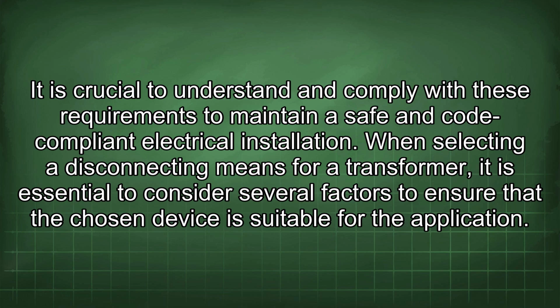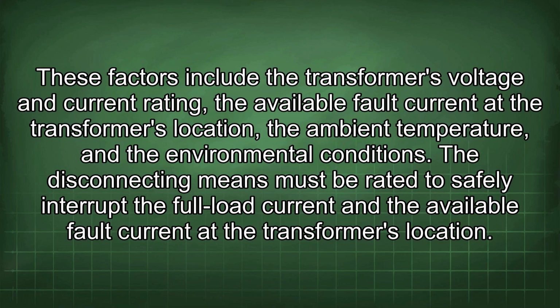When selecting a disconnecting means for a transformer, it is essential to consider several factors to ensure that the chosen device is suitable for the application. These factors include the transformer's voltage and current rating, the available fault current at the transformer's location, the ambient temperature, and the environmental conditions. The disconnecting means must be rated to safely interrupt the full load current and the available fault current at the transformer's location.